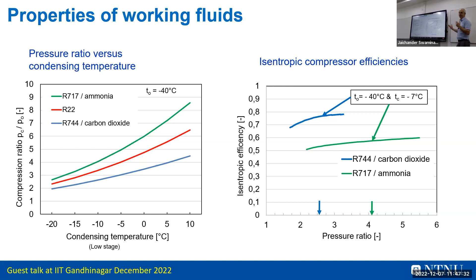Here we can see a traditional condensing fluid, which has the process like in here. While with the CO2, we need to go like this, and then we have this gliding heat rejection, and this is actually a loss. But if we do water heating, we can utilize it. And the next one, where we have a relatively high loss, is the throttling loss, when we throttle in the system. But we can come back to the challenges.